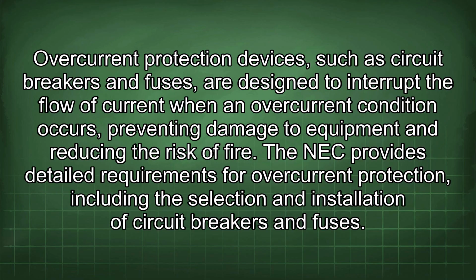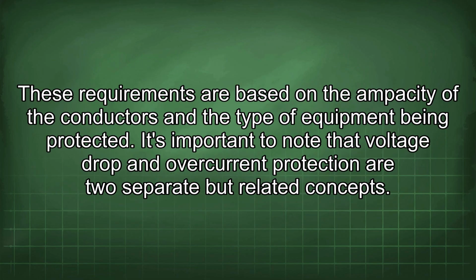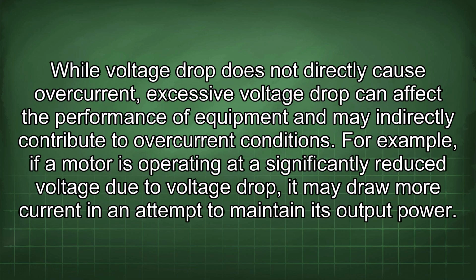The NEC provides detailed requirements for overcurrent protection, including the selection and installation of circuit breakers and fuses. These requirements are based on the ampacity of the conductors and the type of equipment being protected. It's important to note that voltage drop and overcurrent protection are two separate but related concepts. While voltage drop does not directly cause overcurrent, excessive voltage drop can affect the performance of equipment and may indirectly contribute to overcurrent conditions.